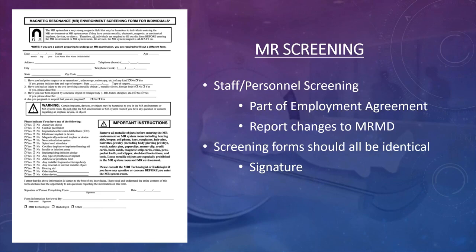When it comes to screening, everyone going anywhere near the magnet must be screened. All screening should be consistent — your screening sheet for patients and for staff should be nearly identical, and your processes should pretty much be the same. On the patient screening sheet you want name, ID, medical history, and weight. Everyone should be screened for any kind of medical implants on or in them, including diabetic pumps and internal implants.